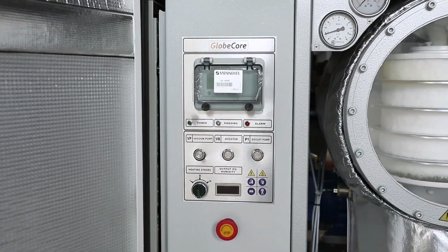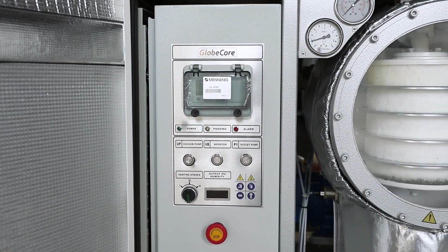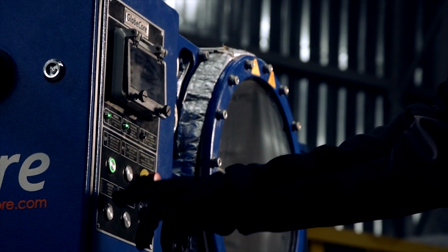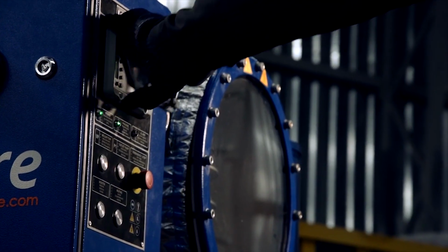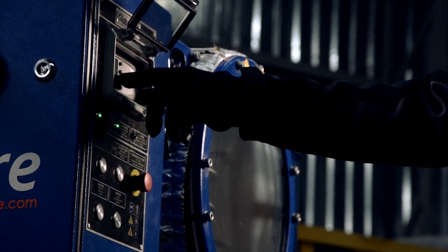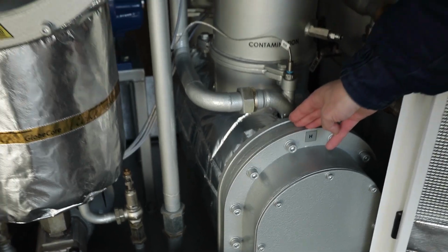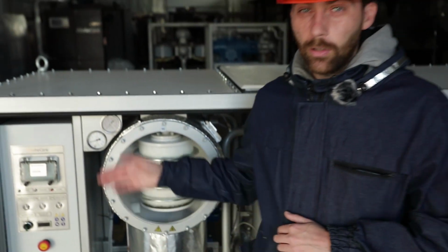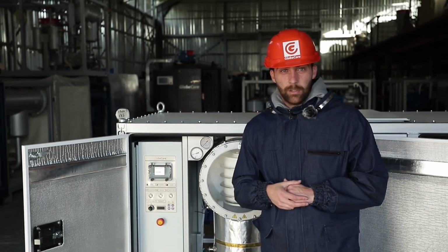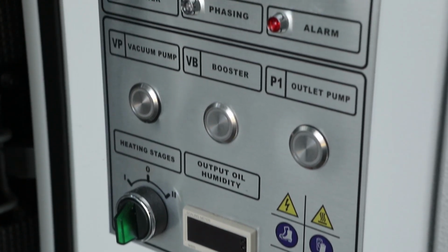It is performed by an operator by turning the heater and the pumps on and off using the control cabinet panel. The heater can be turned on with full or half power. The controller displays important parameters of the purification process, the dielectric liquid temperatures, and the absolute pressure in the vacuum column, as well as the status of actuators and sensors.